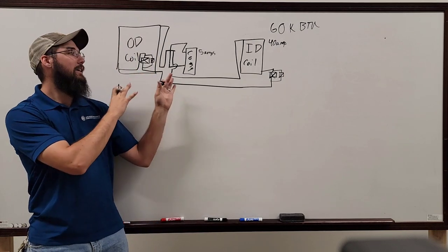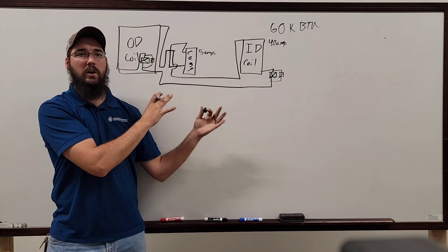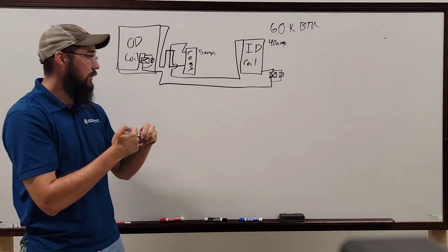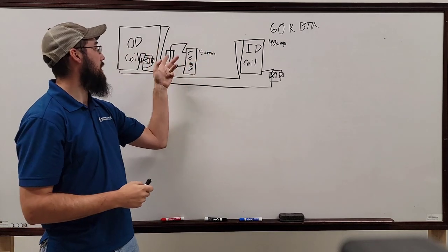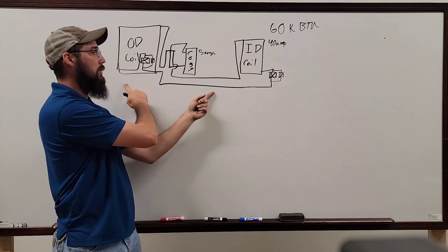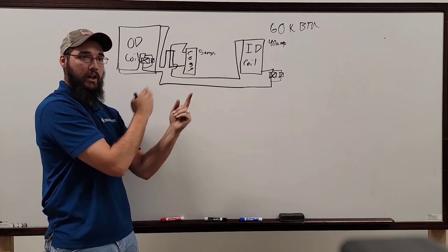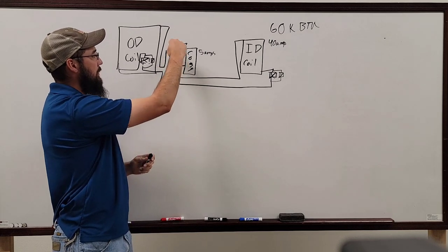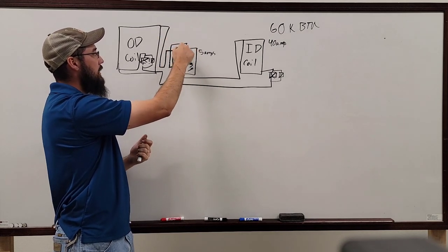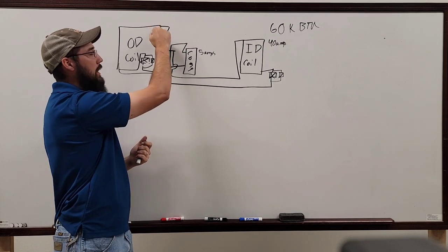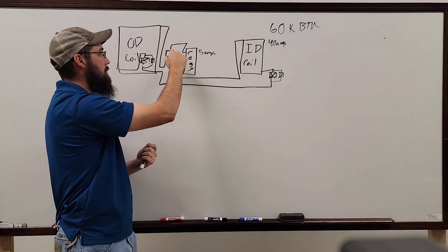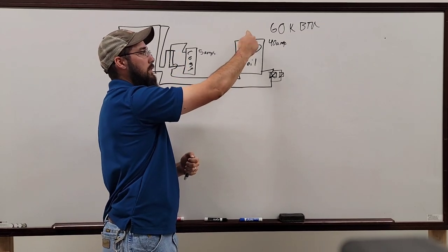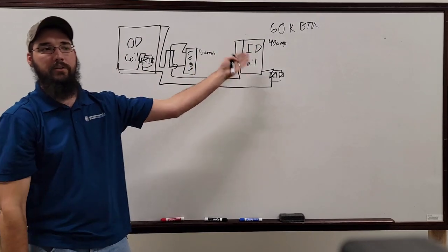The point is, this is the whole concept as to why heat pumps are becoming so prevalent and where they began. In early stages, this is all a heat pump was: this reversing valve reversed the flow. The compressor never changed, but the valve redirects the flow. In regular cooling mode, the discharge line feeds to the top of the outdoor coil. When it switches over to heat mode, we feed the discharge to the indoor coil, which now becomes our condenser, and the outdoor coil becomes the evaporator.